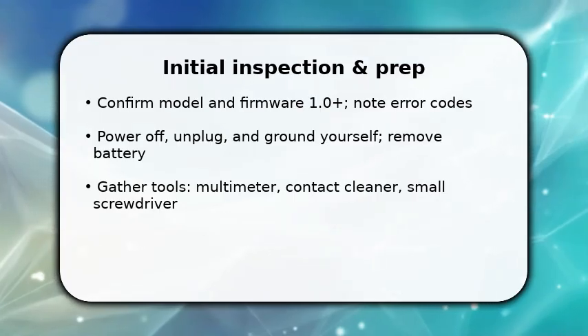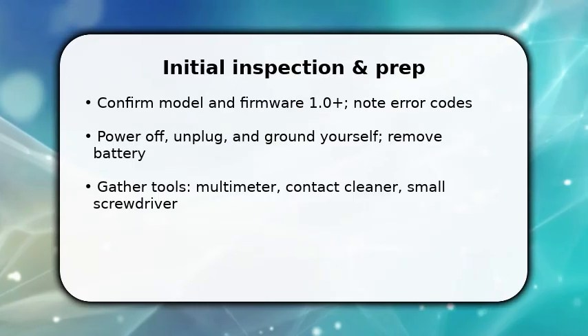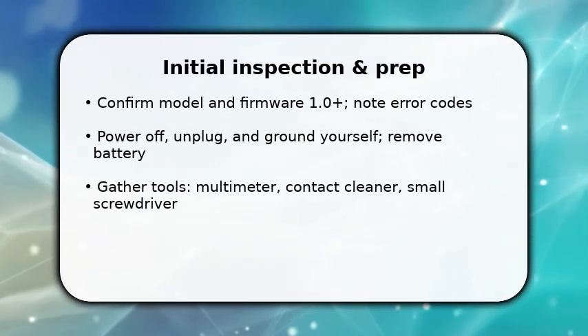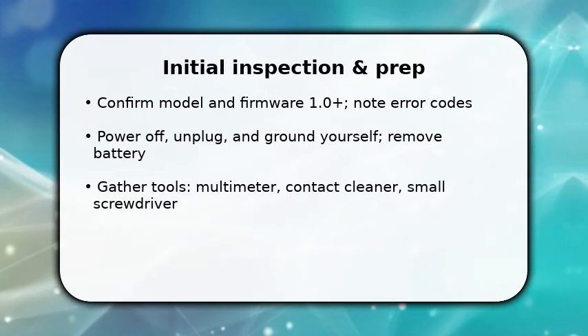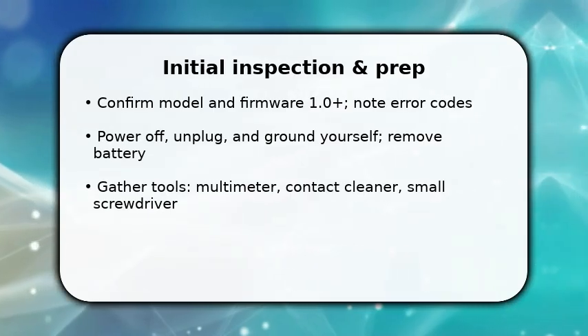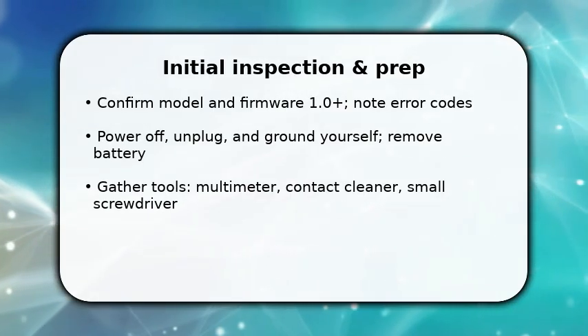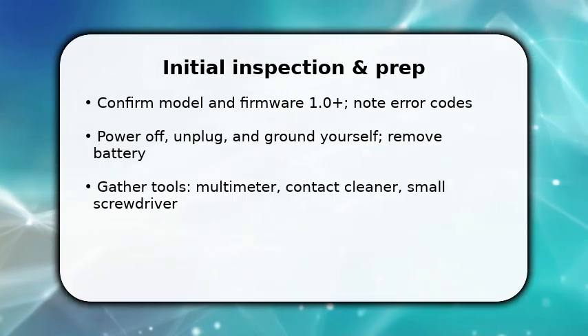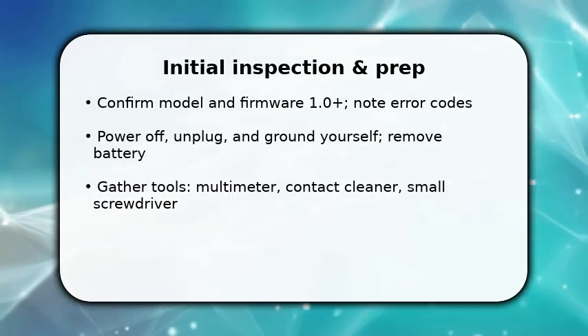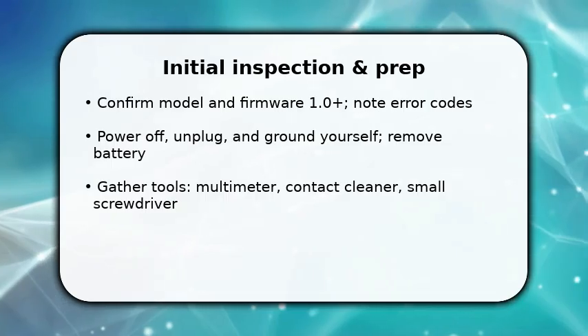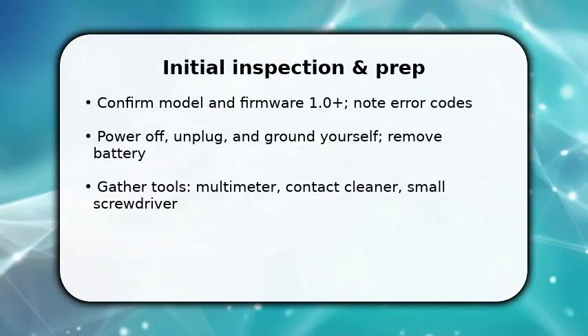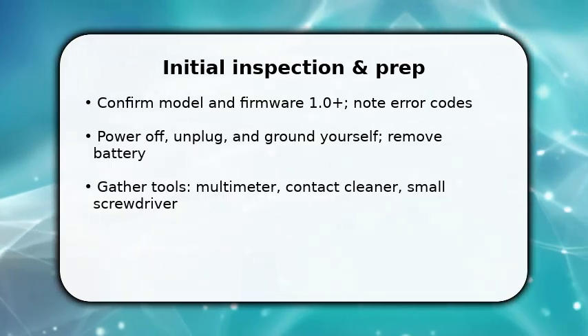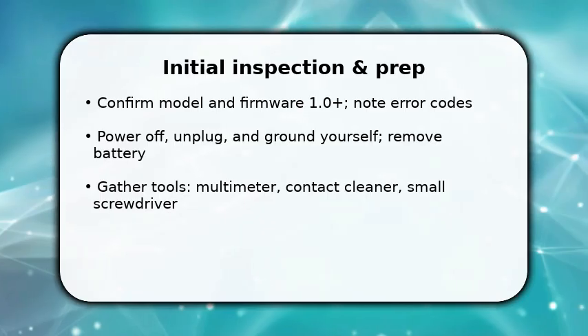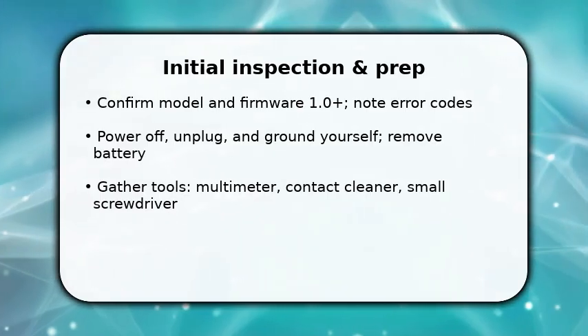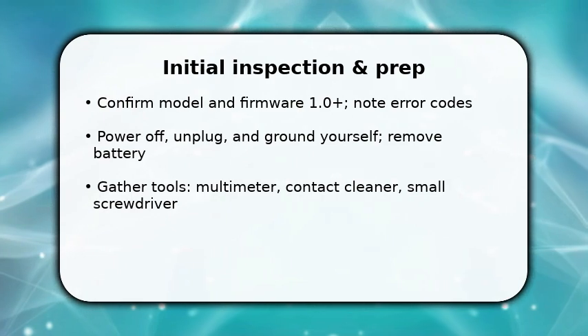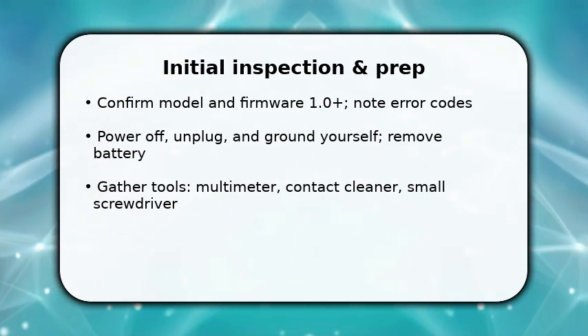You start by combining checks with action. Inspect the unit for burn marks and pull error codes from the display, then power down and remove the battery to prevent surprises. Once done, ground yourself and open the chassis using the correct screwdriver to avoid static damage. You should also check that firmware is 1.0 or newer and have a multimeter and contact cleaner ready, because precise voltage and clean contacts are the foundation of fixing slow, sparking failures.